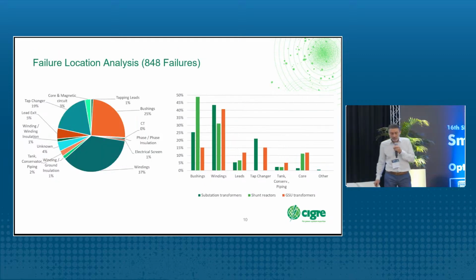We also analyzed the location, so where did the failure occur? And you can see here the biggest percentage is windings, winding to ground insulation, phase-to-phase insulation. So more or less failures in the insulation system. Basically, this is half of the failures. And then we also have failures in bushings and tap changers. This means that for the condition assessment of a transformer, you have to investigate not only the active part, the windings, but also bushings and tap changers. That is important for the condition assessment later.